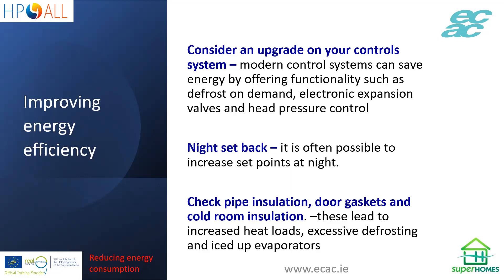Night setback is used quite a lot in commercial refrigeration. When the shop closes at night, you can increase the set point by a couple of degrees and obviously save money. You also want to check pipe insulation, door gaskets, and cold store insulation. The giveaway for breaking-down insulation tends to be condensation or even ice forming on the outside. Door gaskets are incredibly important — bad door gaskets not only let heat in but also let in moisture, which will condense on your evaporator, increasing the amount of defrost required and decreasing the efficiency of the whole system. Door curtains and anything to keep the cold store sealed will all help.